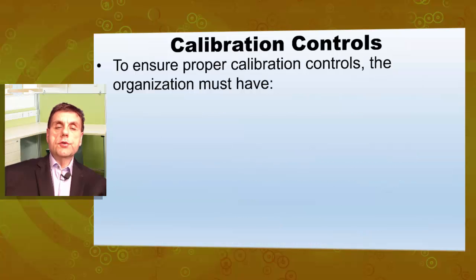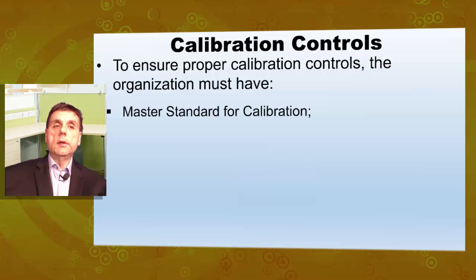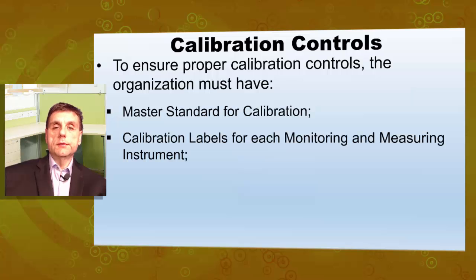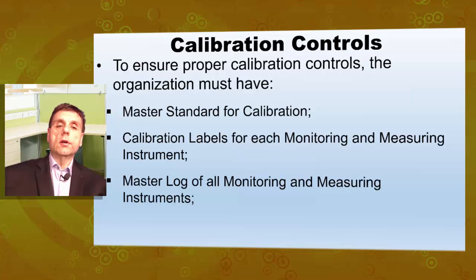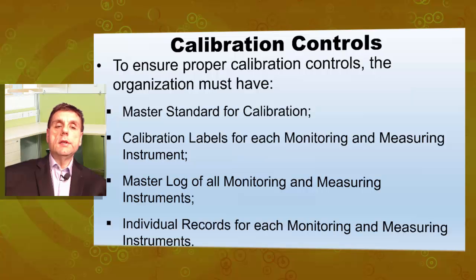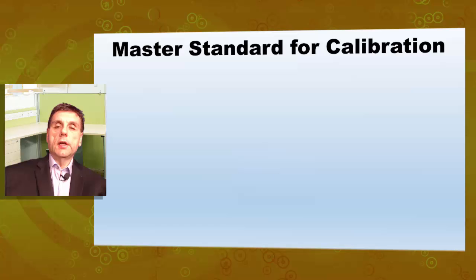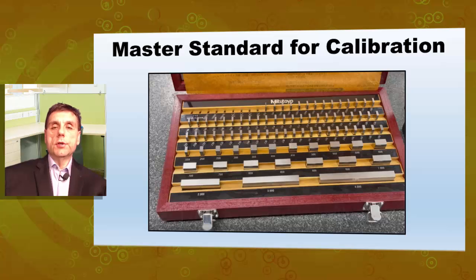Calibration controls. To ensure proper calibration controls, the organization must have a master standard for calibration, calibration labels for each monitoring and measuring instrument, a master log of all monitoring and measuring instruments, and individual records for each monitoring and measuring instrument. A master standard for calibration could be the master gauge set, which is presented here in the slide. So these blocks, the calibration blocks that are externally calibrated or rather verified, can be used for the internal calibration because they are of known accuracy. So this is just an example, right, of a master set that can be used for the internal calibration.